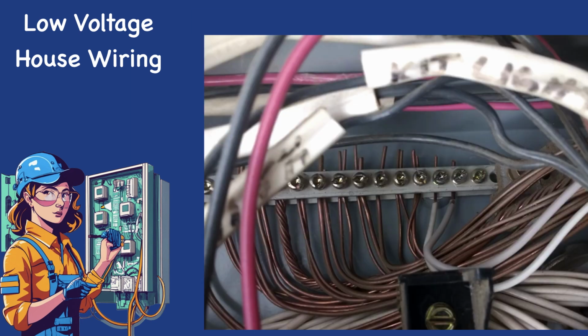The grounding pathway is generally formed by a system of bare copper wires that connect to every device and every metal electrical box in your home. In standard sheathed NM cable, this bare copper wire is included along with the insulated conducting wires inside the cable. The bare copper grounding wires terminate in a grounding bar in your main service panel, and that grounding bar is in turn connected to a grounding rod driven deep into the earth outside your home.